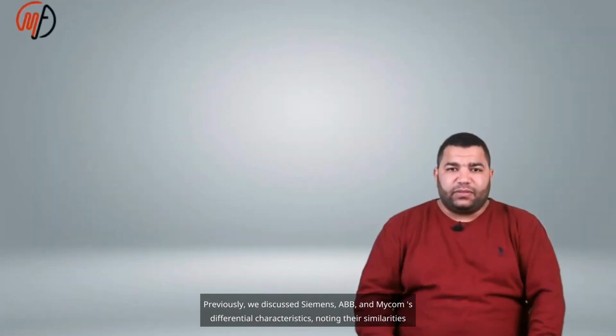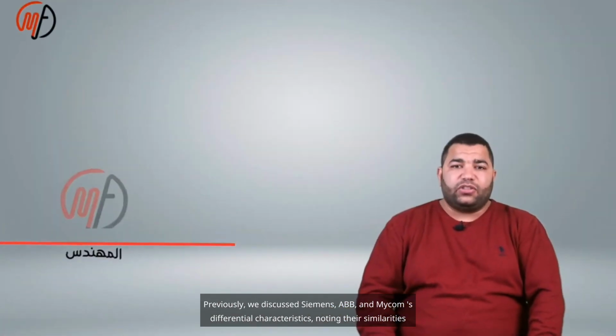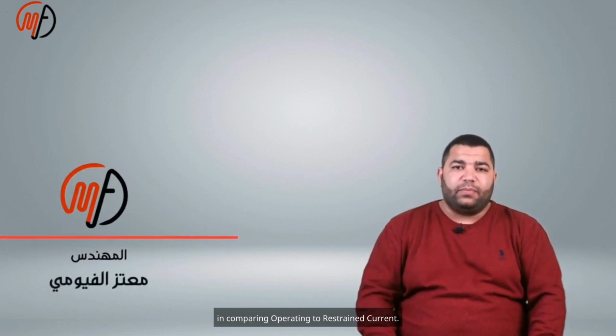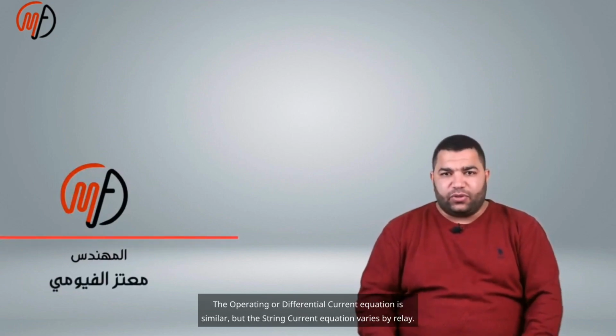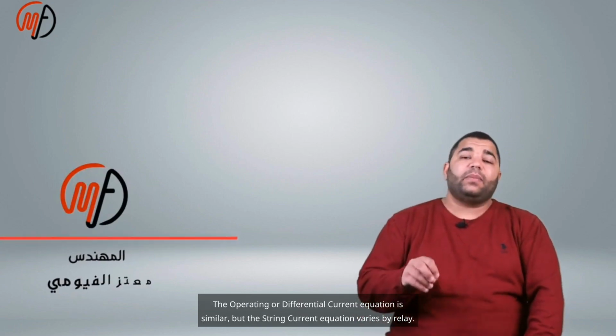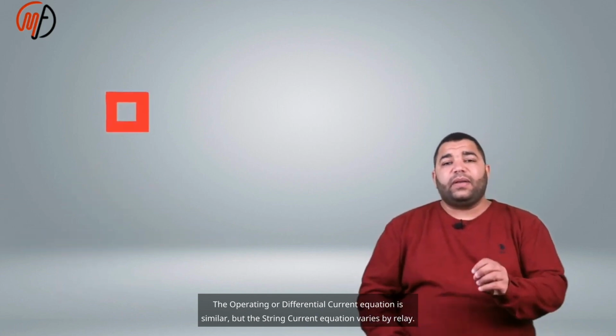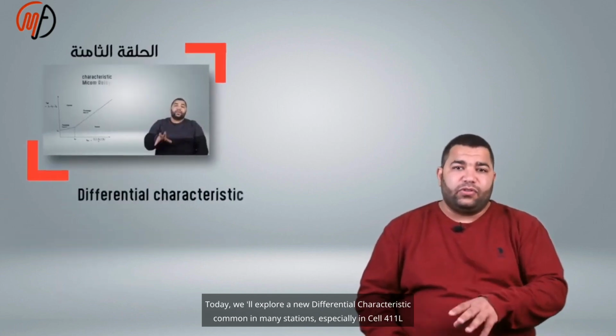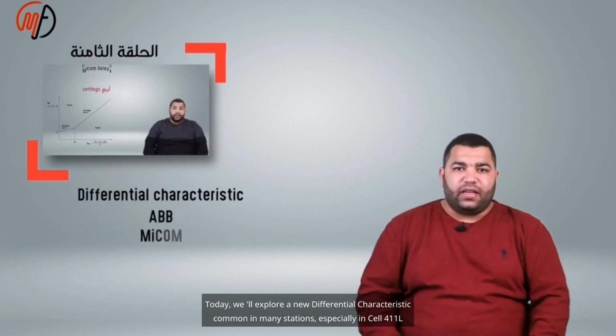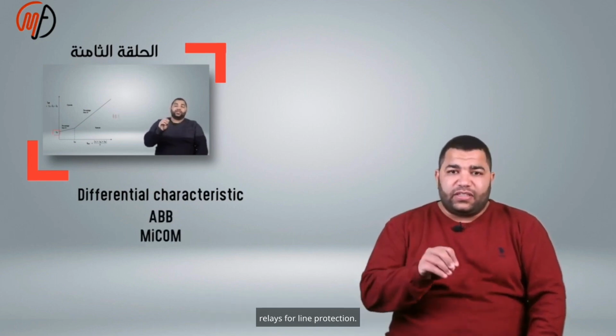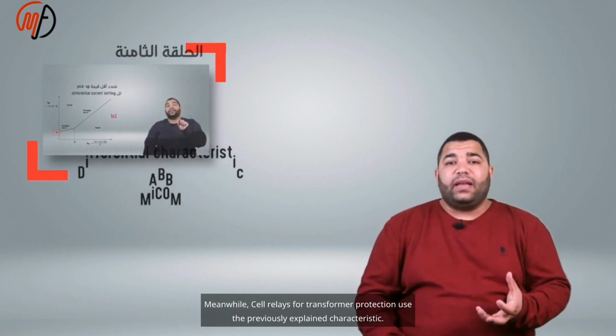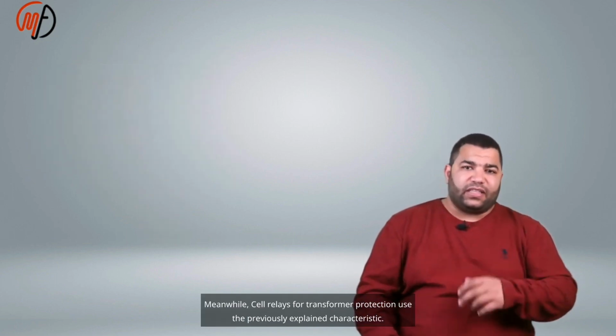Previously, we discussed Siemens, ABB, and MICOM's differential characteristics, noting their similarities in comparing operating to restrained current. The operating or differential current equation is similar, but the restraint current equation varies by relay. Today, we'll explore a new differential characteristic common in many stations, especially in SEL-411L relays for line protection. Meanwhile, SEL relays for transformer protection use the previously explained characteristic.